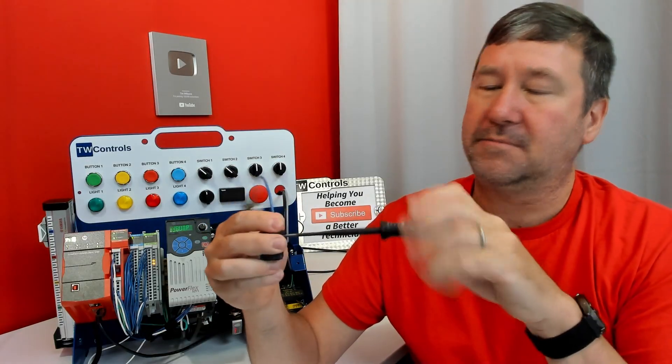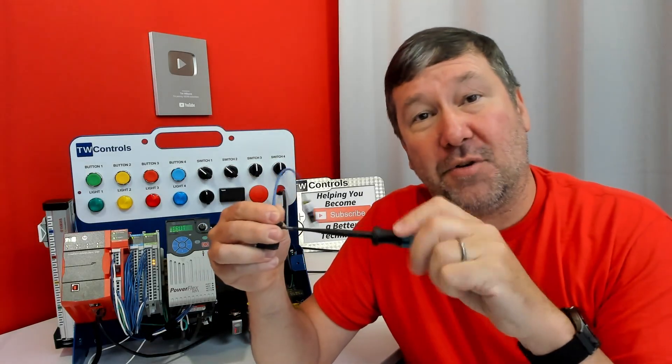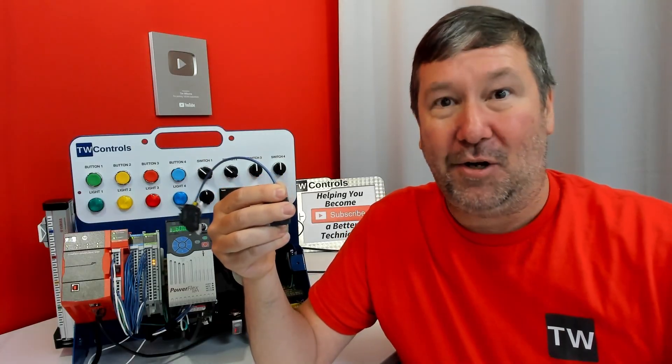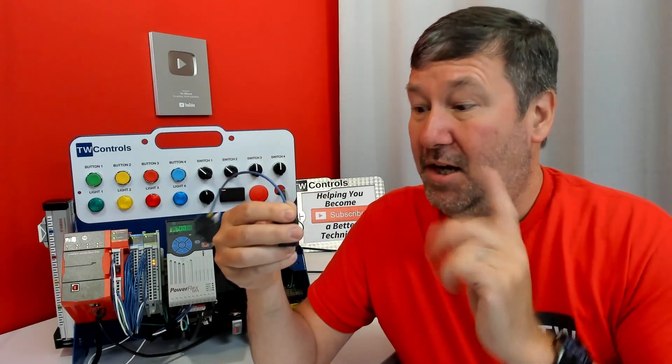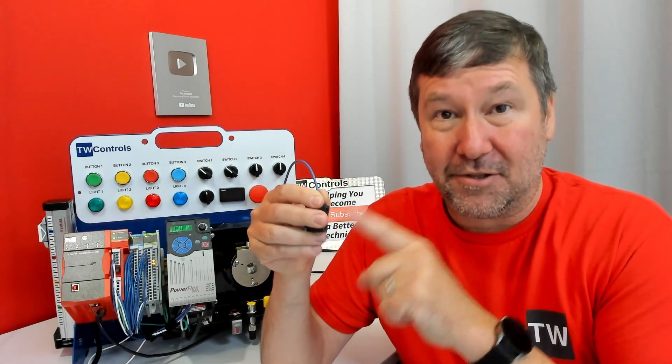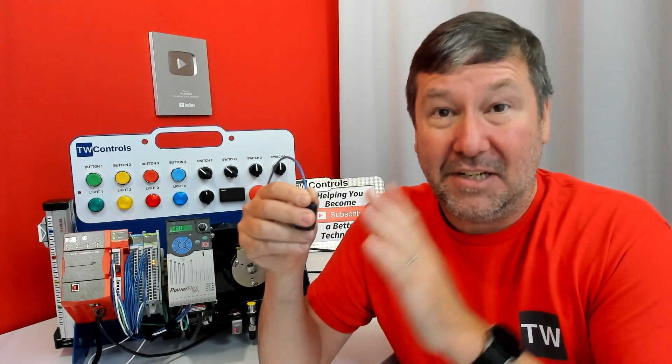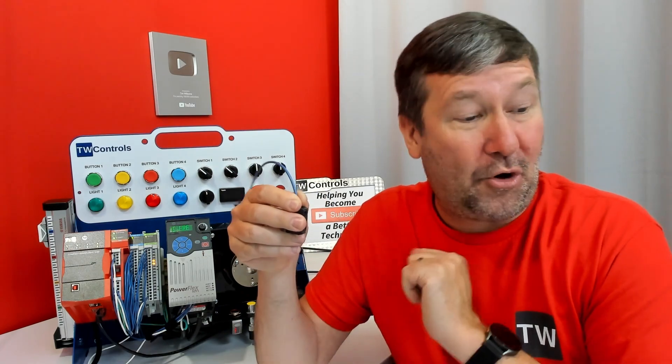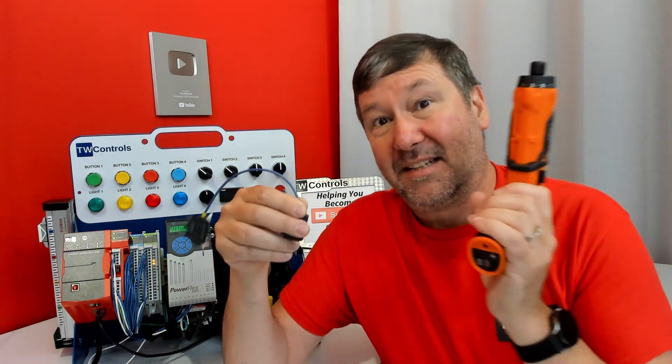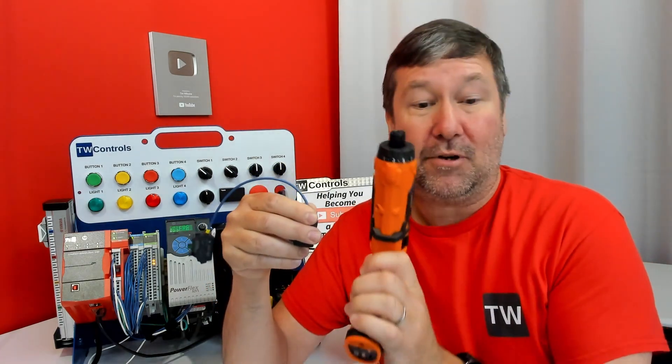Pop a wire down, tighten the screw up, and we're done. But we're not actually done. Per UL, every screw terminal in your control panel needs to be torqued.